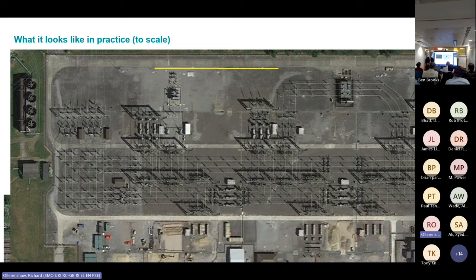Hambleton Junction is the biggest of the SFCs, the biggest one in the world feeding 25 kV railway. Come back to that later. So the grid substation here has two SFC blocks, each roughly 80 MVA in rating. That's an instantaneous rating. The continuous rating is a little bit lower. And then the 25 kV switchgear. So of the order of 60 metres by 60 metres.